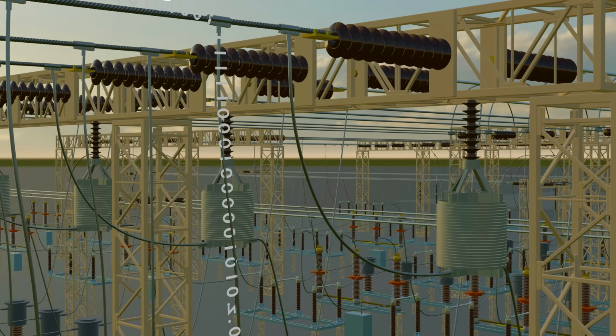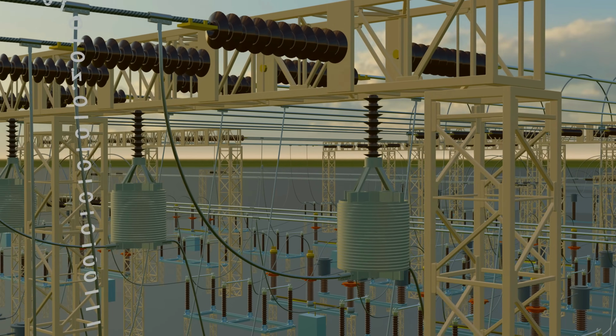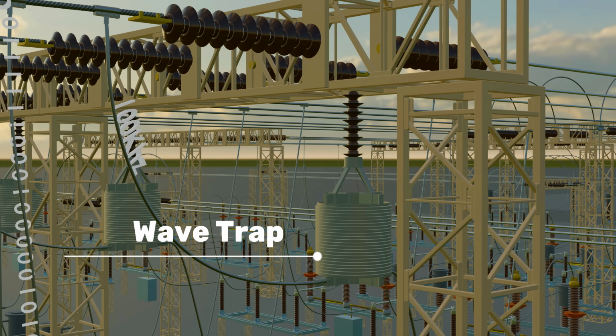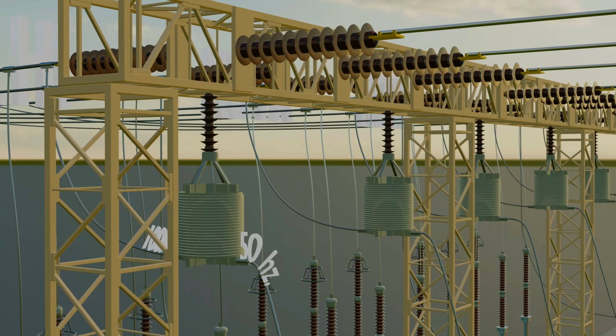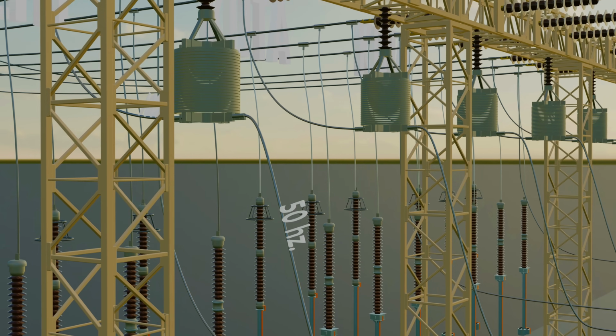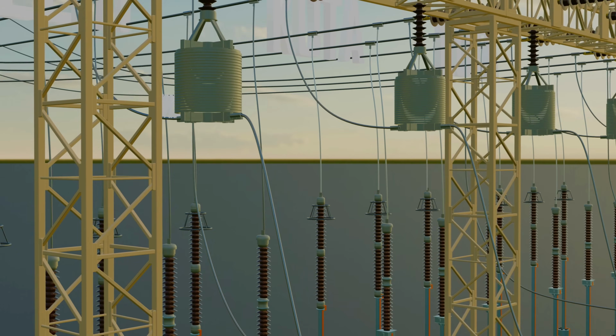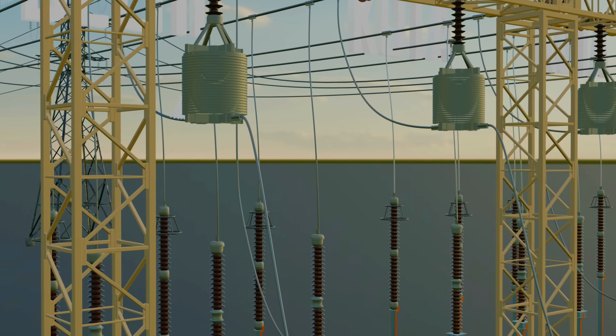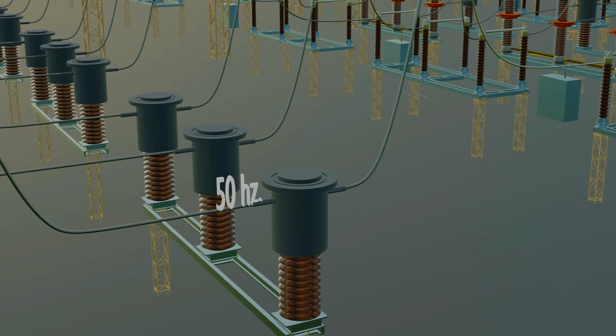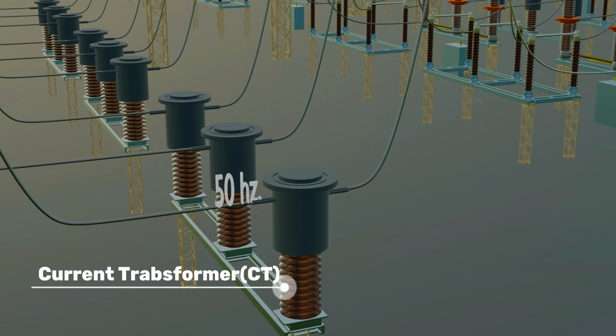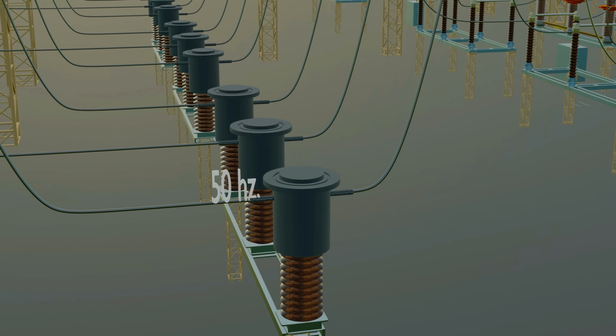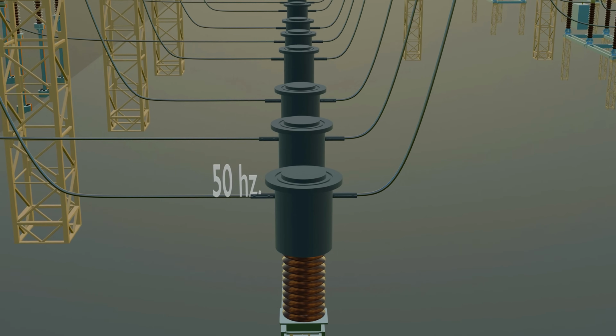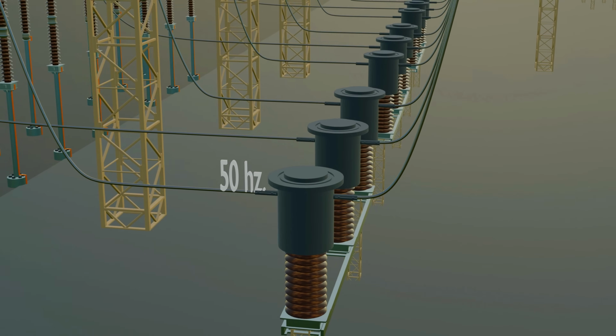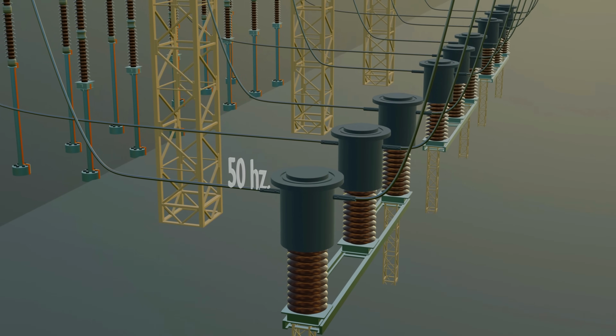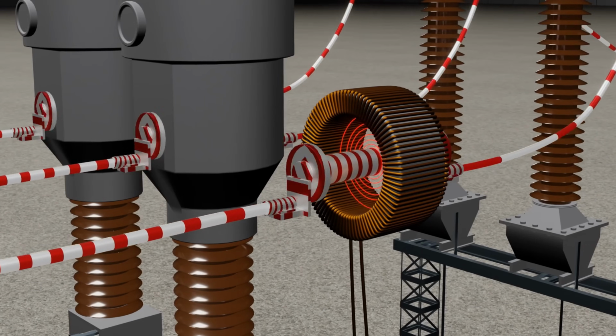To ensure that only 50 Hz power reaches consumers, a device called a wave trap is installed in series with the line. It blocks all high-frequency communication signals, allowing only standard 50 Hz power to pass through. From here, electrical power flows towards a current transformer. This device measures the current in the line. If a fault occurs and current suddenly rises, the current transformer, or CT, detects and reports the spike.